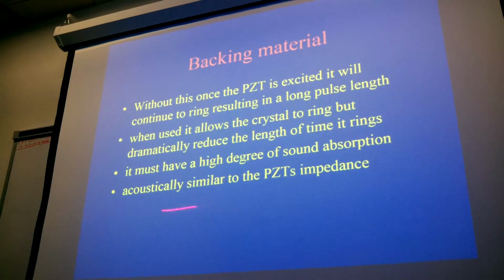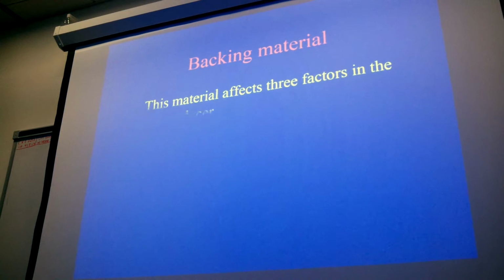Acoustically similar. The reason the backing material has to be acoustically similar to the crystal impedance is that it prevents that back and forth. Because the crystal doesn't know you want it to go that way. It's going to go that way too when it's sending the sound. If it's similar, it's not going to create that reverberation that's going back and forth. It'll have the same sound into it, so it doesn't create the back and forth motion.